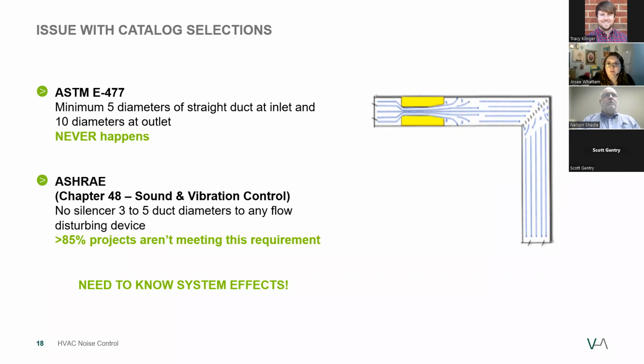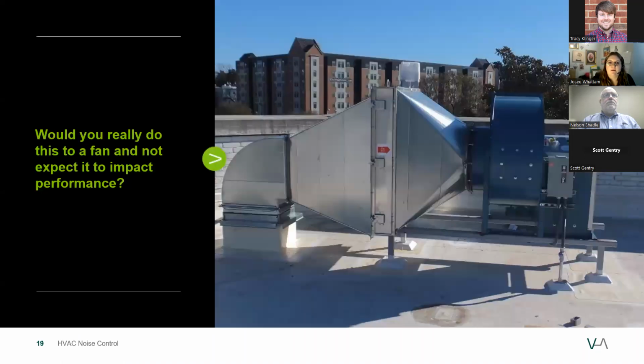Unfortunately, the numbers in the catalog and the softwares are only accurate if the above guidelines are followed. If that's not possible, then the information in the catalogs become completely incorrect. So without an analysis of actual operating conditions, the real noise attenuation is unknown. So we need to know the system's effects. Would you really do this to a fan and not expect it to impact performance? We have the same issue when it comes to silencers. So best practice is applied engineering.